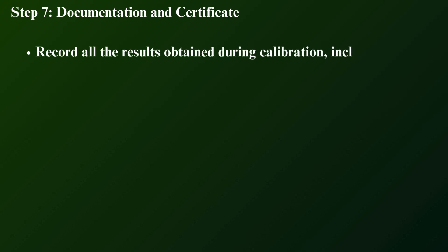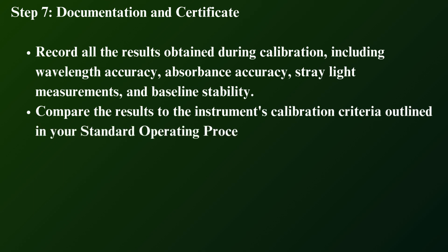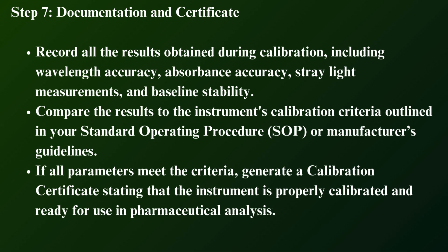Step 7: Documentation and certificate. Record all the results obtained during calibration, including wavelength accuracy, absorbance accuracy, stray light measurements, and baseline stability. Compare the results to the instrument's calibration criteria outlined in your standard operating procedure or manufacturer's guidelines. If all parameters meet the criteria, generate a calibration certificate stating that the instrument is properly calibrated and ready for use in pharmaceutical analysis.